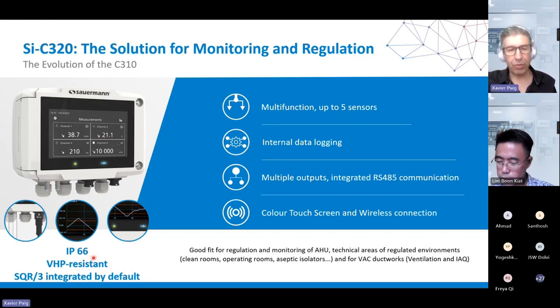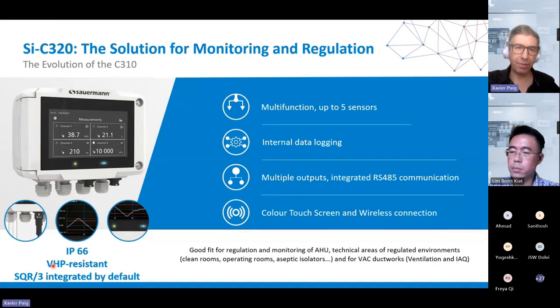We also have improved a lot the mechanical side. Now we have IP66. Before it was IP65, so we have increased the rate of protection on the instrument. The front face is also VHP resistant. VHP means vaporized hydrogen peroxide. That's the cleaning agent used in many clean rooms, for example. When they clean the walls of the clean room or the machines, they use this type of chemical, which is really aggressive. Now, these instruments are ready to withstand this VHP application.